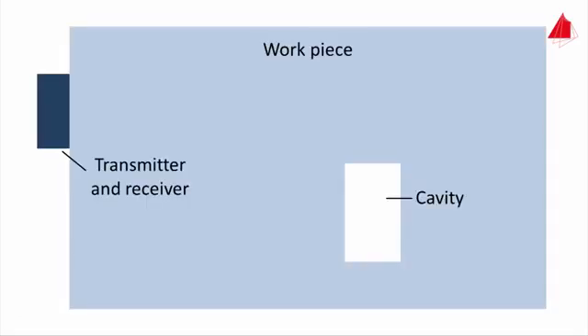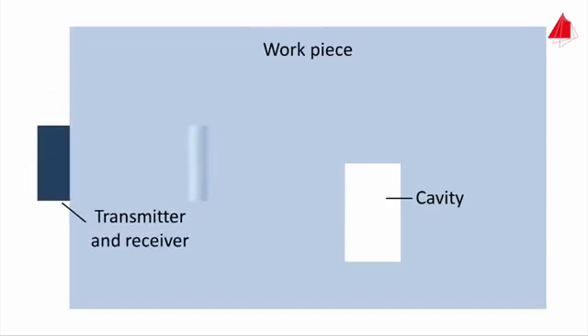For ultrasonic testing of a workpiece, not a large transmitter is used in most cases, but a rather compact one which generates a short ultrasonic pulse. At a place free from defects, the ultrasonic pulse travels to the right front end, also termed back wall. The pulse is reflected and recorded again as an echo. When the transmitter is moved a little downwards, the cavity reflects a part of the wave that arrives earlier at the transmitter than the rest of the sound wave. Even further downwards, the cavity reflects the complete ultrasonic pulse.